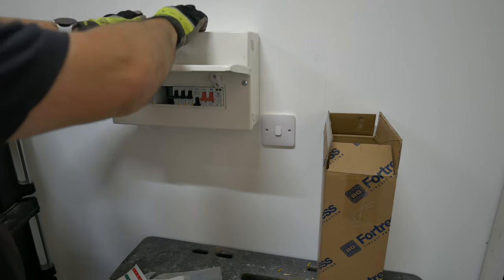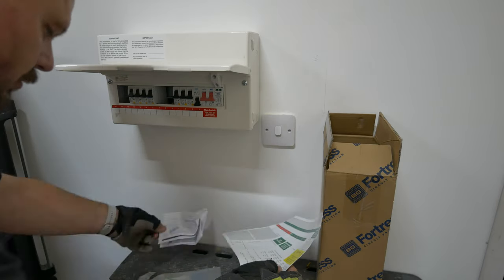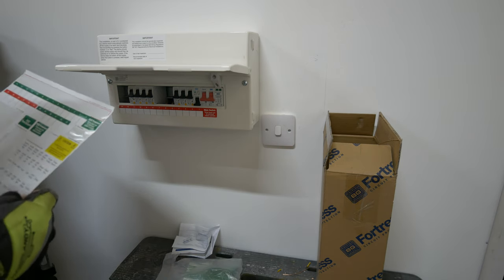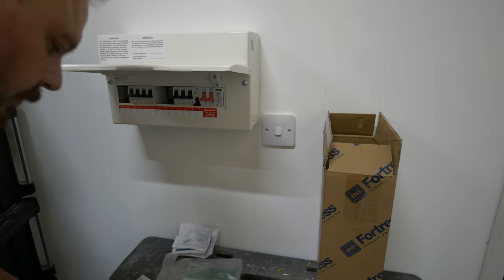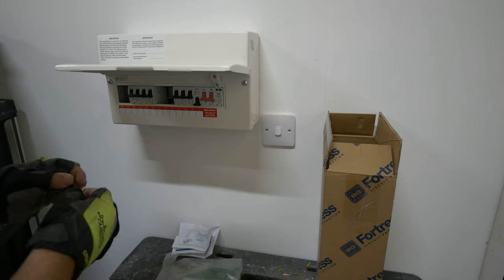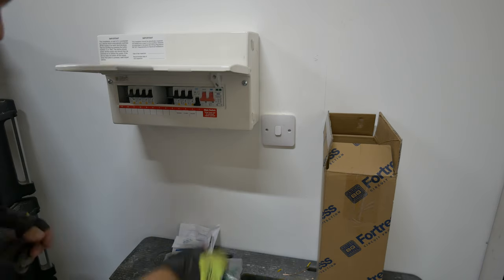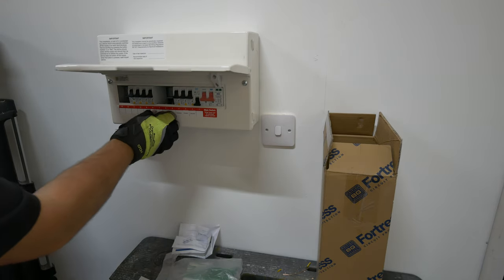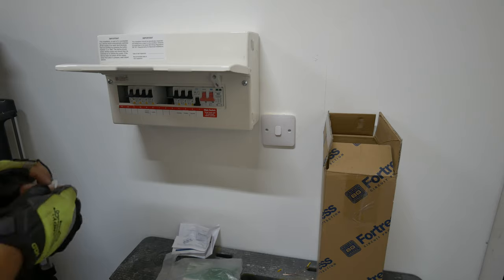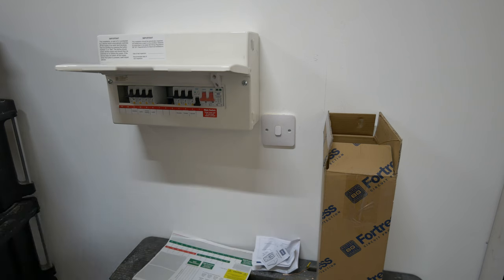The BG board does come with a clever little tool to lock the front cover open, which was handy. They do say to leave that with the board - it's magnetic - but my own view is to take it away because you can guarantee a consumer will leave it open permanently. The label sheet is a little bit lacking as I'll talk about later on in this video. I think it's just an older variety of label sheet that maybe hasn't been updated for a while. Generally speaking we'd use our own label printers anyway, but I just like to try and give the boards a good run-out and see what comes in the kit. I think it came together quite nicely and I'm happy with the outcome.